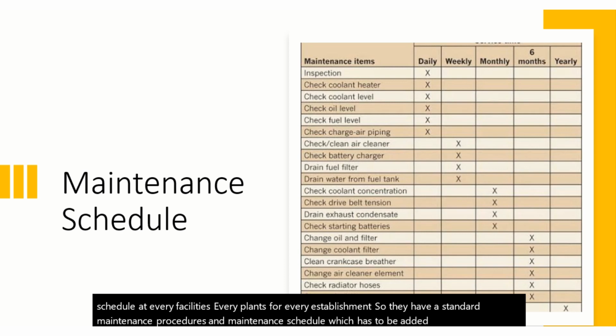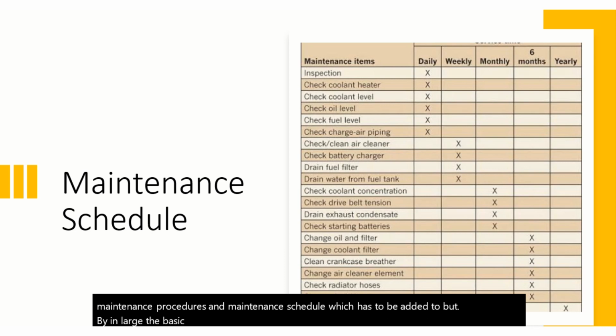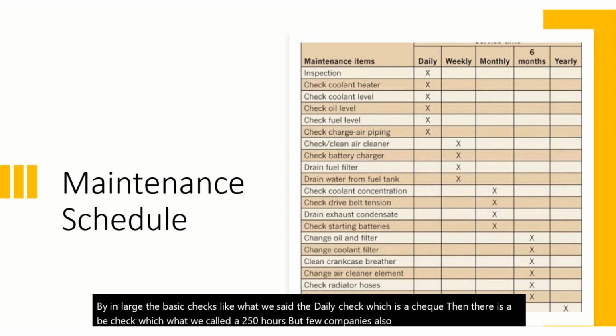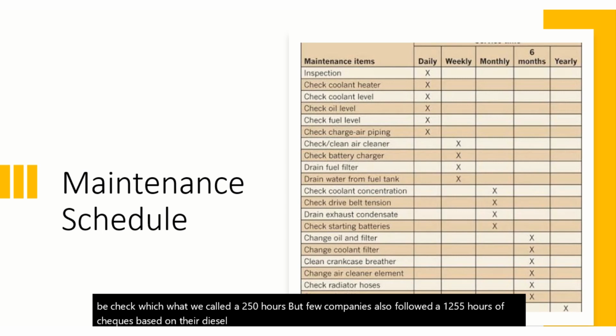But by and large, the basic checks, like what we said, the daily check, which is an A check, then there is a B check, which is what we call 250 hours. But a few companies also follow 125 hours of checks based on their diesel generator location and their running conditions. So A check, B check, C check, and D check is by and large a worldwide standard of the DG set. Like A is daily.